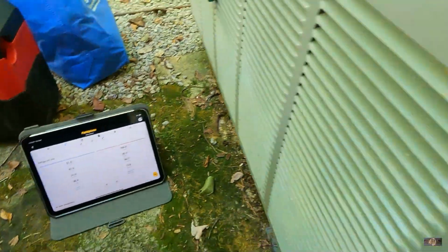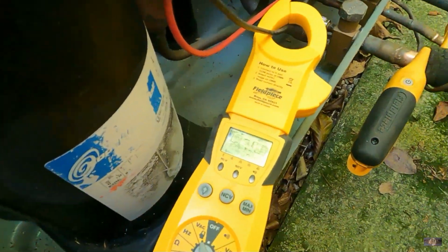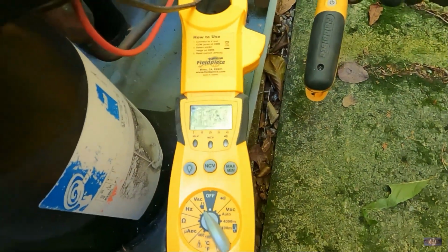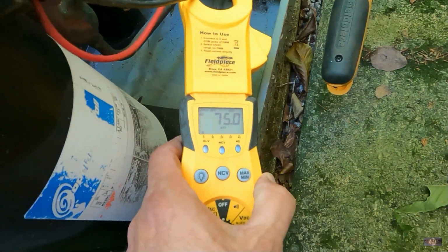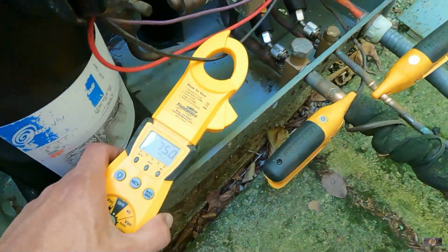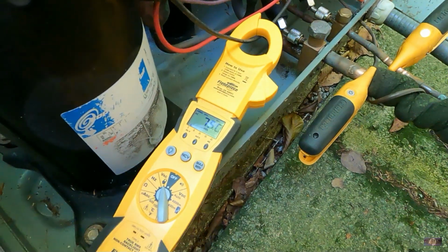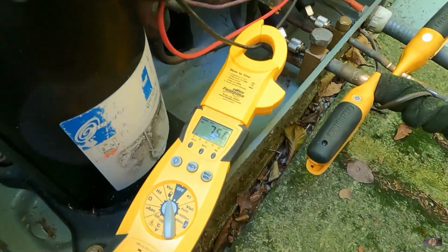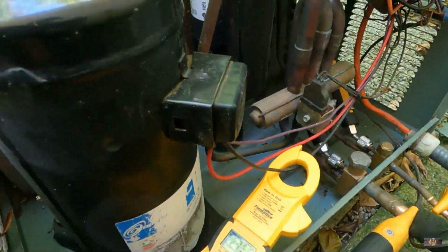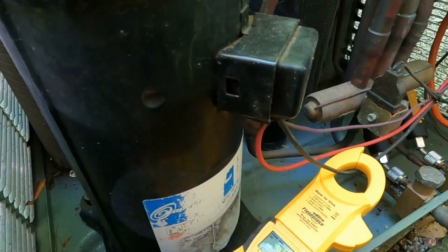So let's get started. Alright, so I fired it up, took an inrush on the compressor, got 75 amps at startup. Not sure if you can see that. There you go, that's probably better. Locked rotor is 84, so it's starting to chooch up. You can tell this thing, when it was first installed, was running really, really hot.